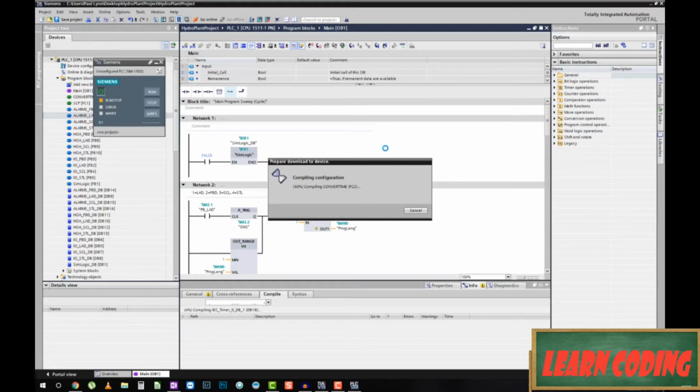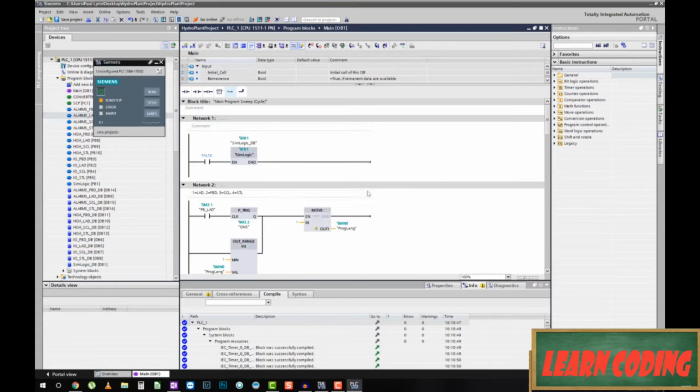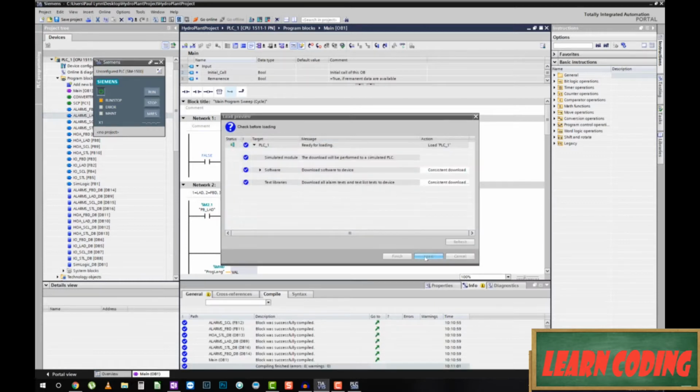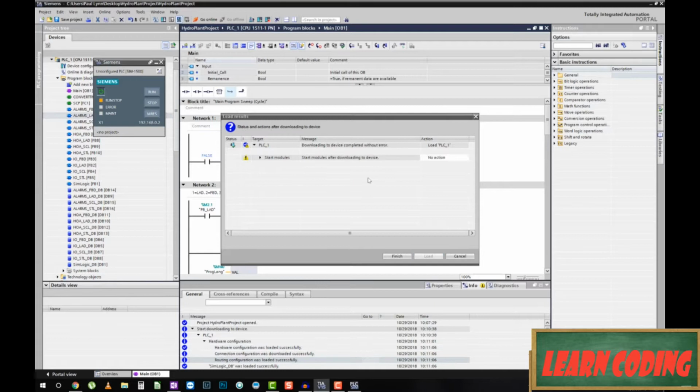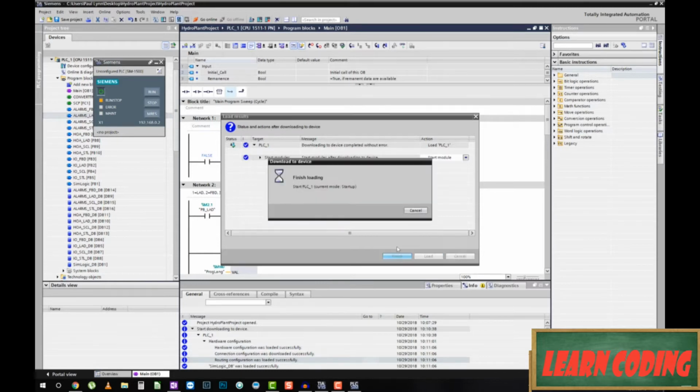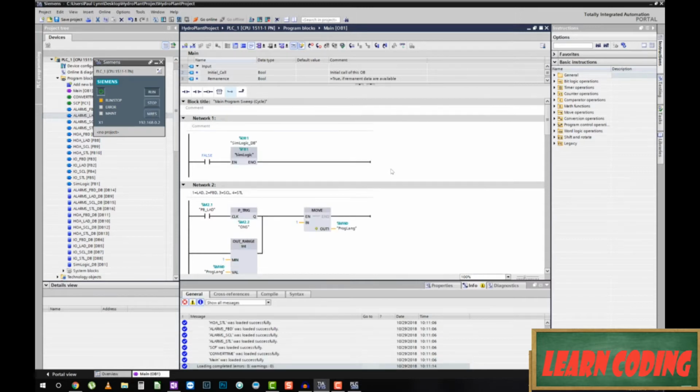While I was editing some of the videos yesterday, I did notice a few mistakes. I don't remember if it was in my ladders or my function blocks, and I didn't go back and fix those. Nothing that would stop it from compiling, but when we try to run the system, I saw some things that would stop us. Basically alarms with reverse polarity, like maybe we were looking for the RPMs to be higher than the overspeed value instead of lower. Just wonky little stuff like that.